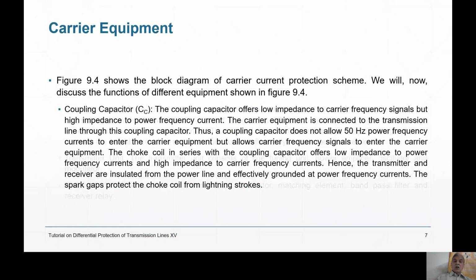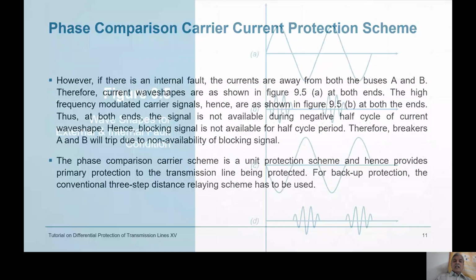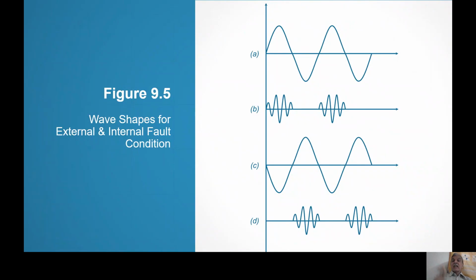So if you plot the curves, if you see the wave shape, it is like this at A, but at B it is like a C, because it is 180 degrees phase shifted, because current is flowing towards the bus. Now the current that is flowing is rectified and modulated. So the wave shape at A which you see is rectified and modulated as shown at B. So the negative cycle is clipped. Only the positive cycle will appear. At B, at the other substation, it will also be rectified and modulated.